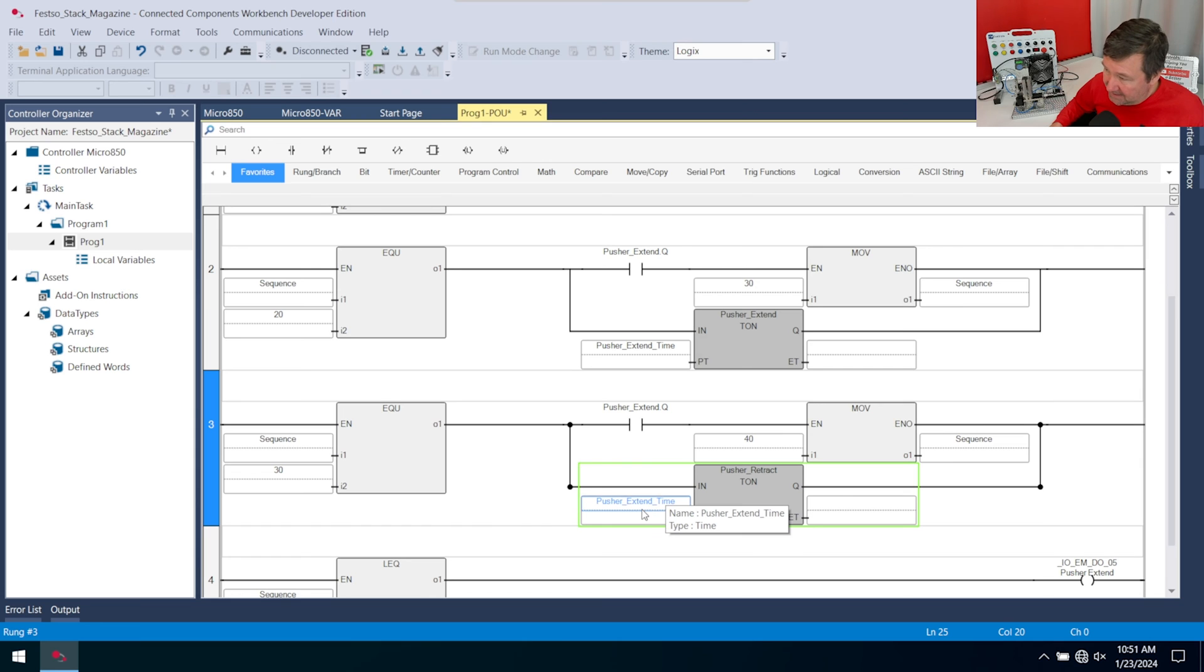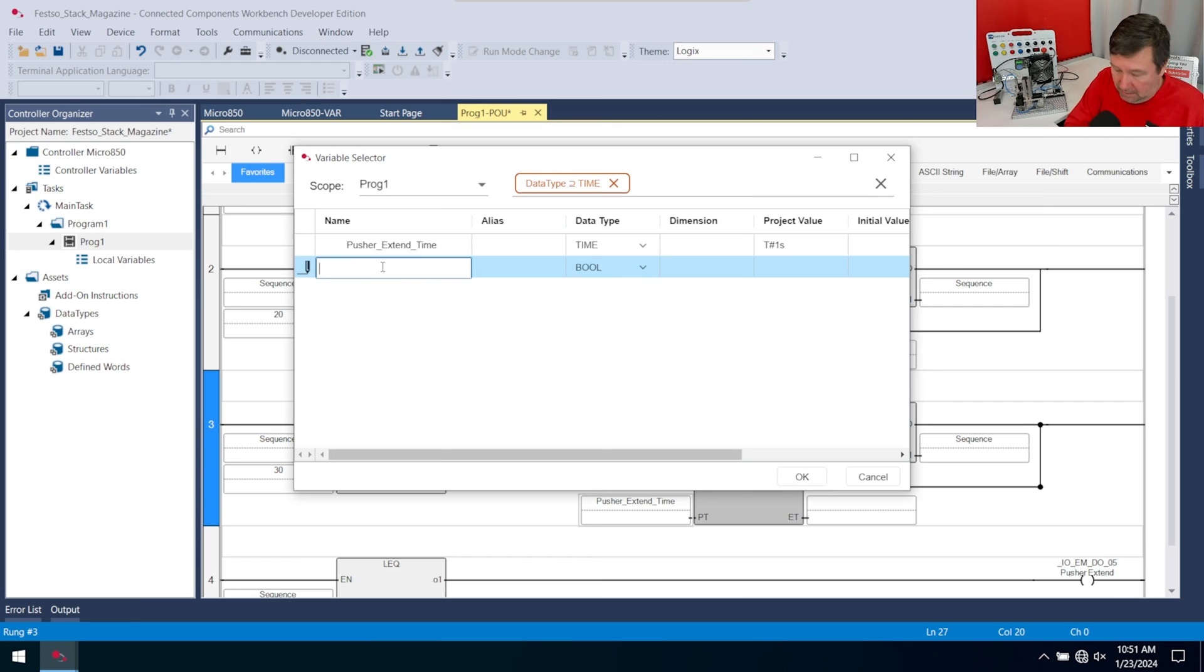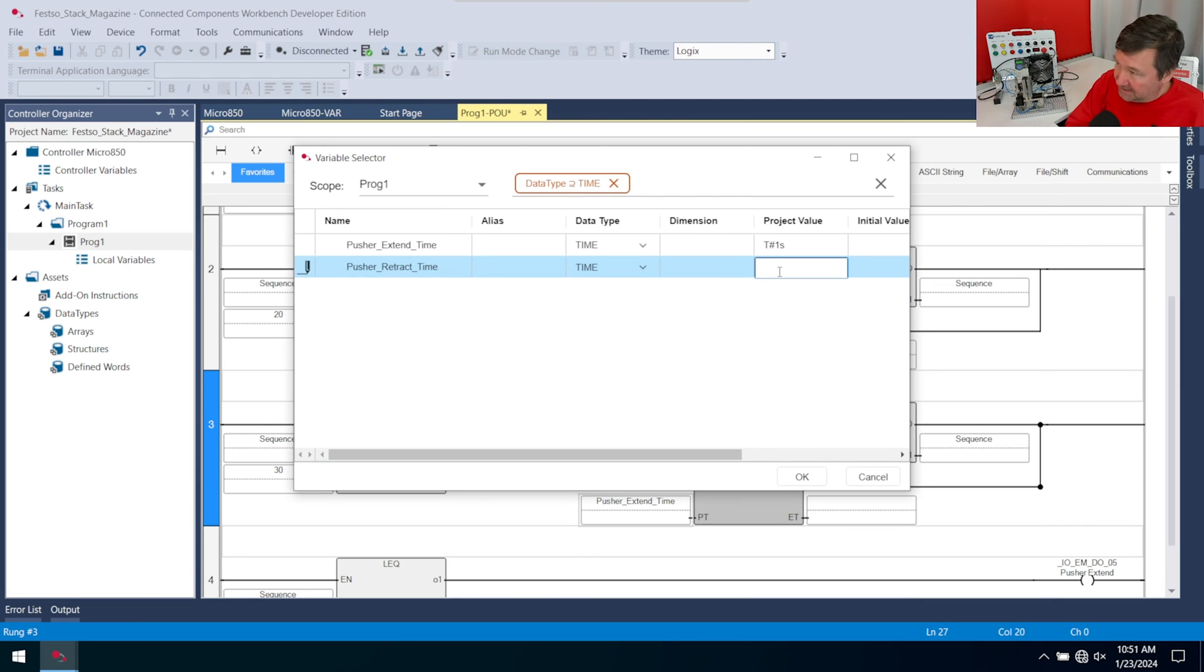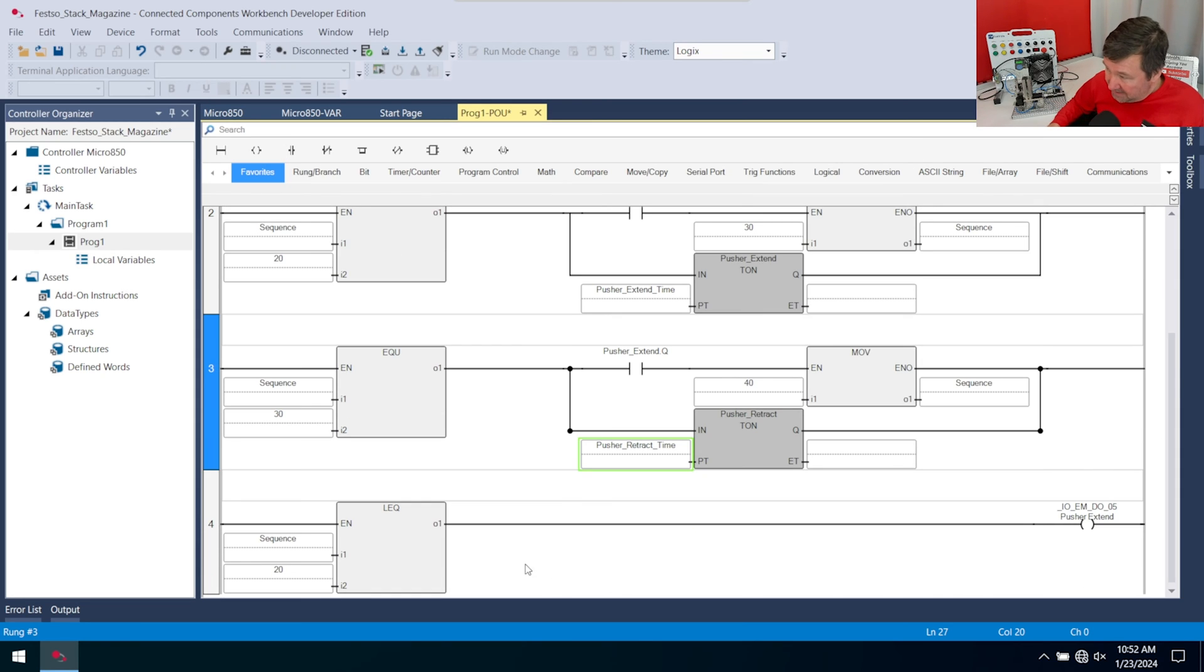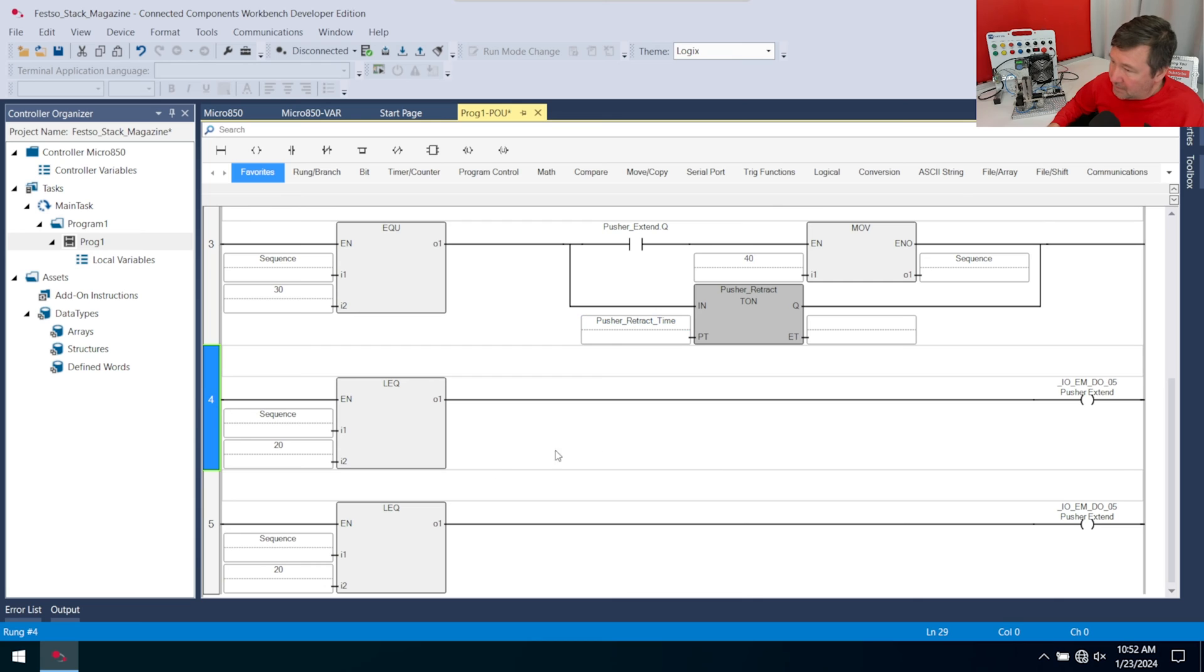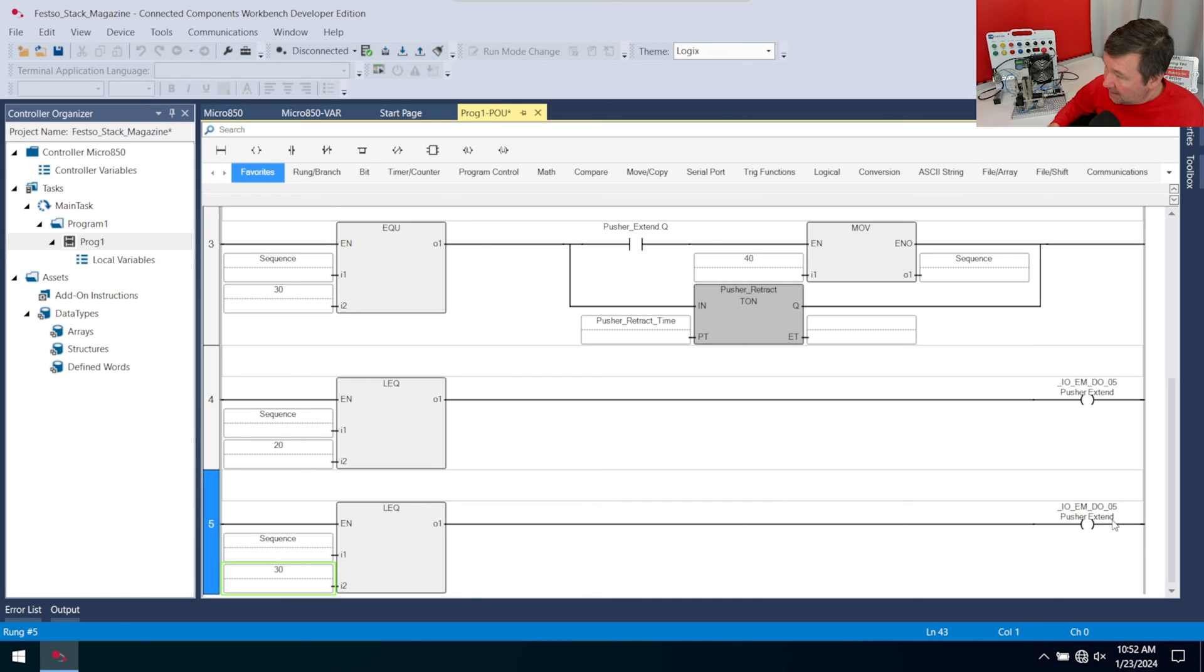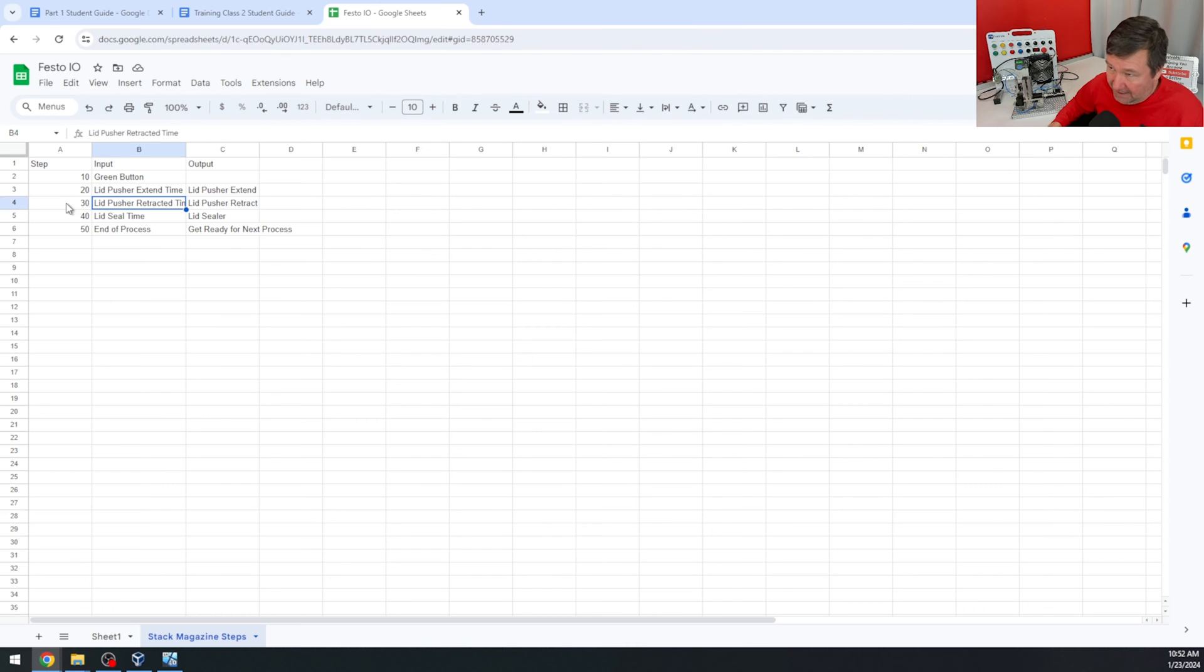We're going to double click on this TON and at the bottom rename it to pusher retract. Then this will not be the extend time anymore. We're going to double click on the bottom of it and click the new pusher retract time. That data type will be time. Very similarly, we found out in the previous video this needed to be about one second, so for my project value I'm going to put T number one S. That's almost the same as what we have here, so we're going to right click for copy and right click and paste.